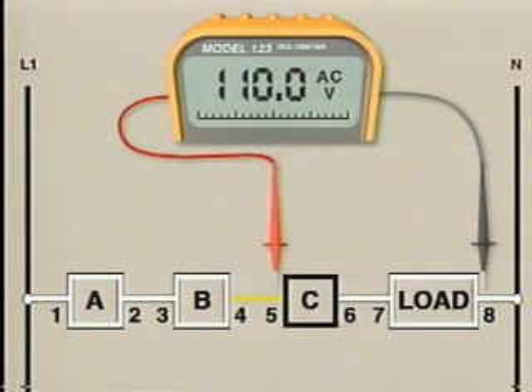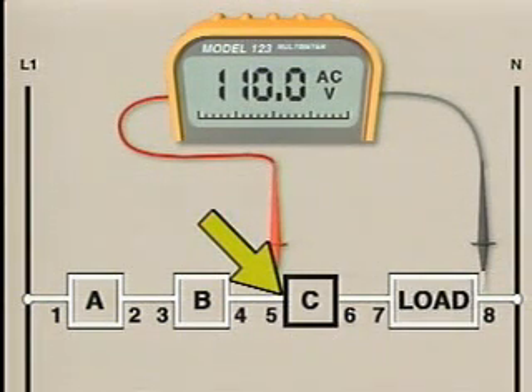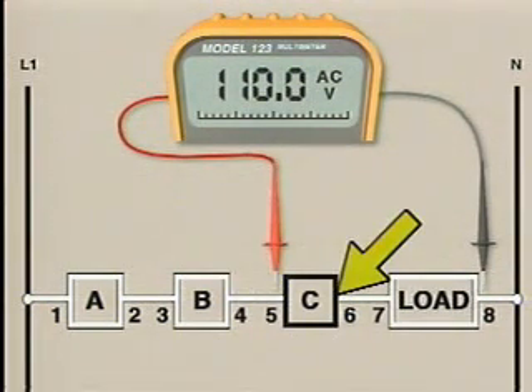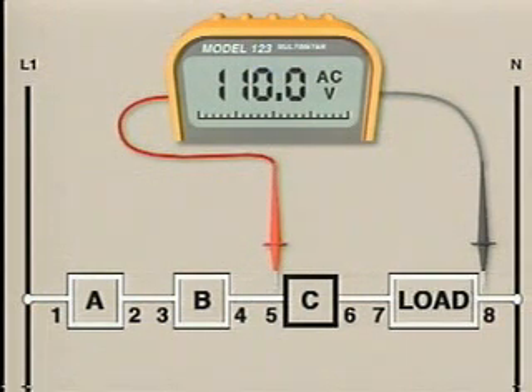This time the voltmeter indicates full line voltage. This means that the circuit's operating voltage is reaching test point 5. Because there is voltage at test point 5, we can eliminate the wire connecting control device B to control device C as a possible cause of the problem. At this point, we've eliminated all of the components in the circuit except for control device C. Control device C is the only circuit component that is between test point 5, where the voltage was present, and test point 6, where the voltage was not present. Working through the circuit using the process of elimination has identified control device C as the cause of the problem.